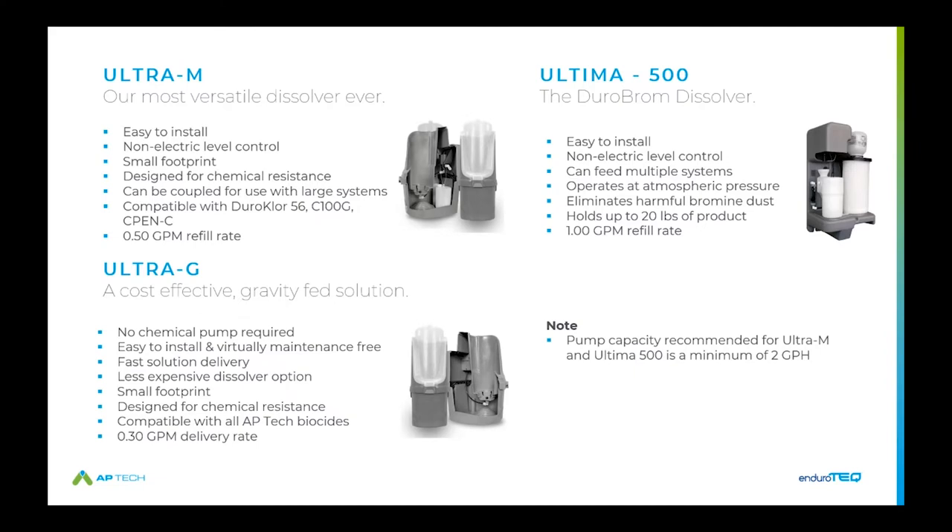The Ultima 500 is designed specifically for DuroBrom or BCDMH. DuroBrom has a lower solubility than other products, and soaking aids in getting the material into solution. This unit provides soaking time and can load up to 20 pounds of product with a high refill rate. The advantage over traditional brominators is that it operates under atmospheric conditions — you're not concerned with pressurization. Brominators are tried and true devices and remain another option for delivering BCDMH, though we wouldn't recommend brominators with our DuroBrom product specifically.